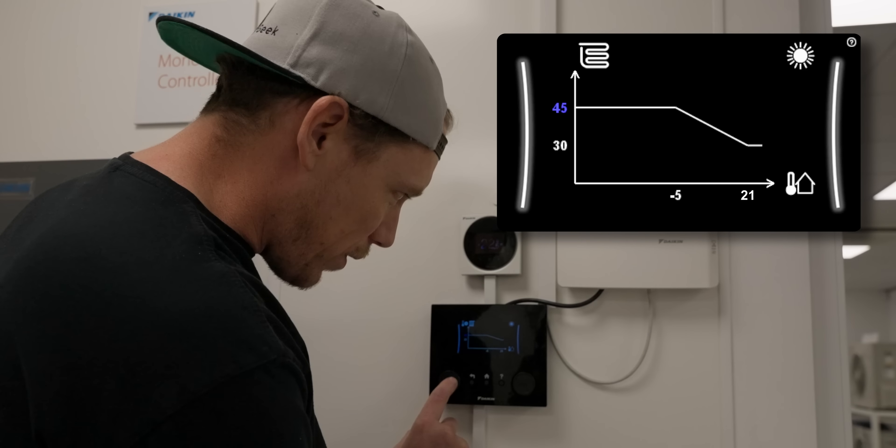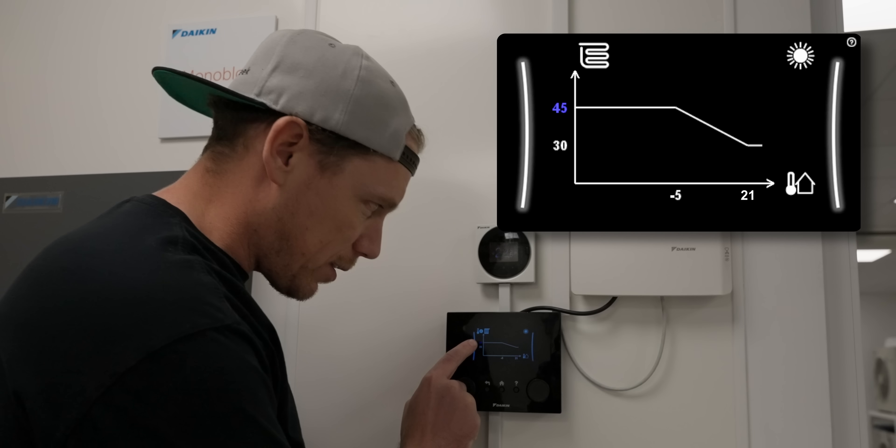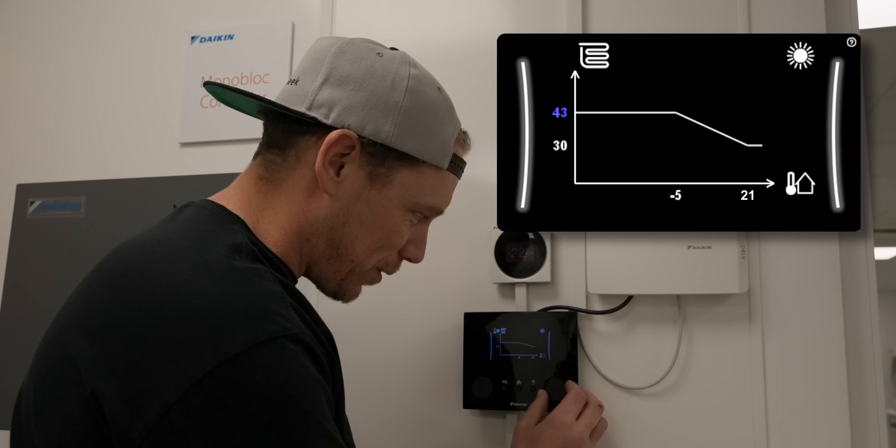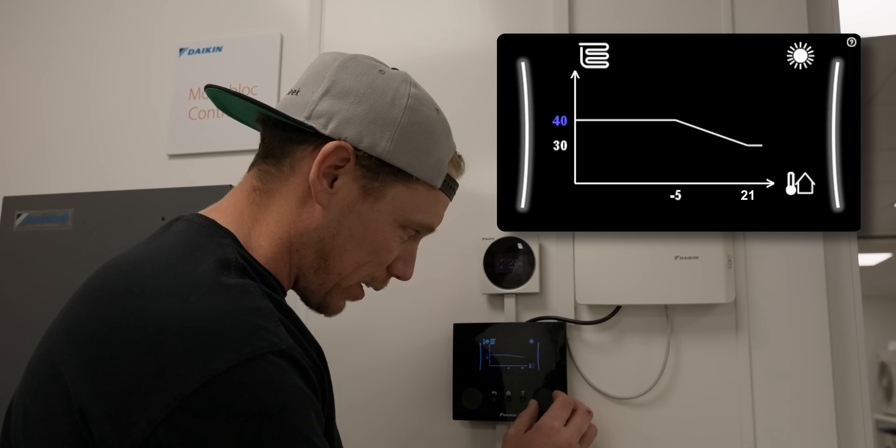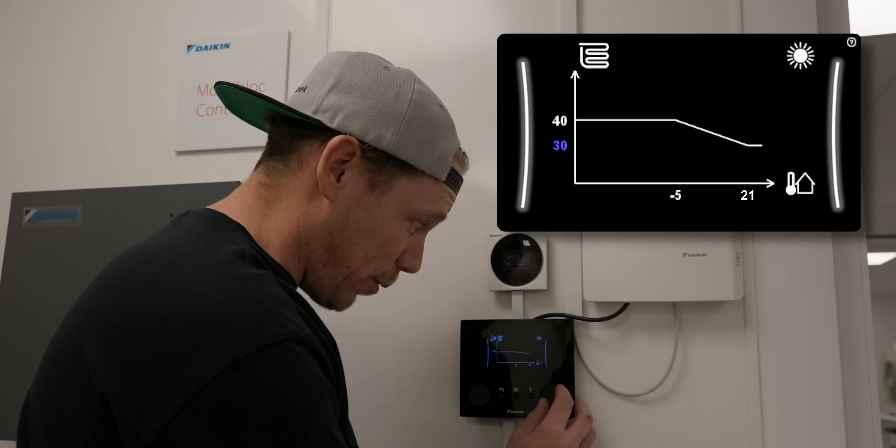WD curve, weather dependent curve. What we do here is typically we'd select 45 and we turn this down to whatever our system design temperature is. So if we design our systems for a maximum flow temperature of 40 degrees, we turn this down to 40.